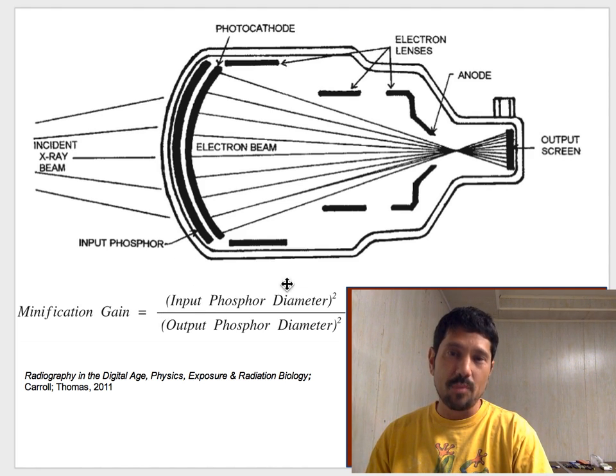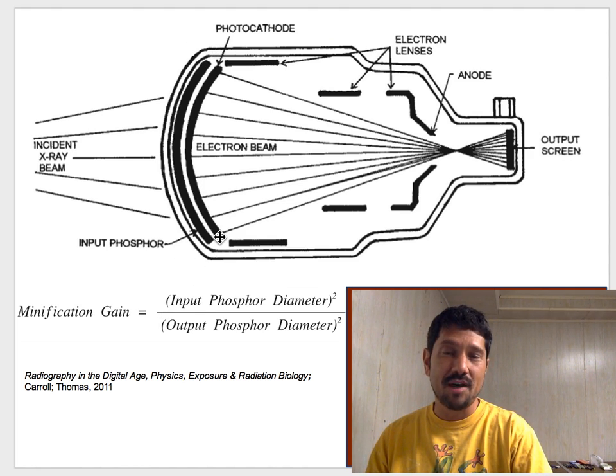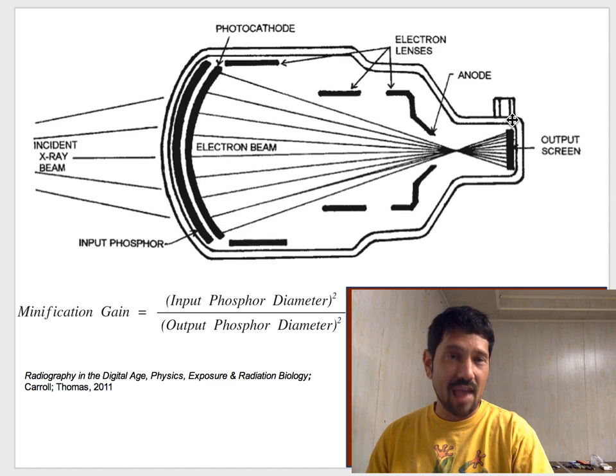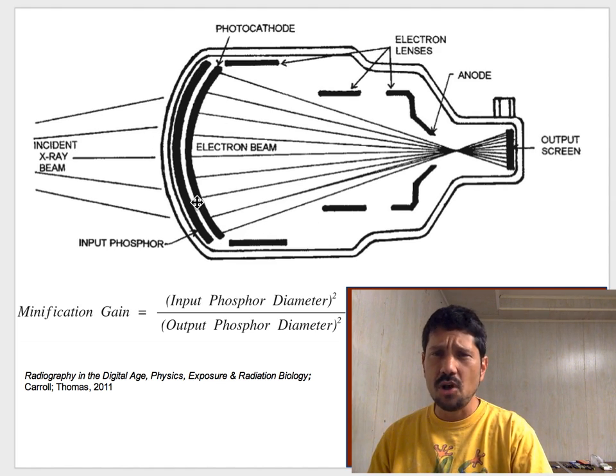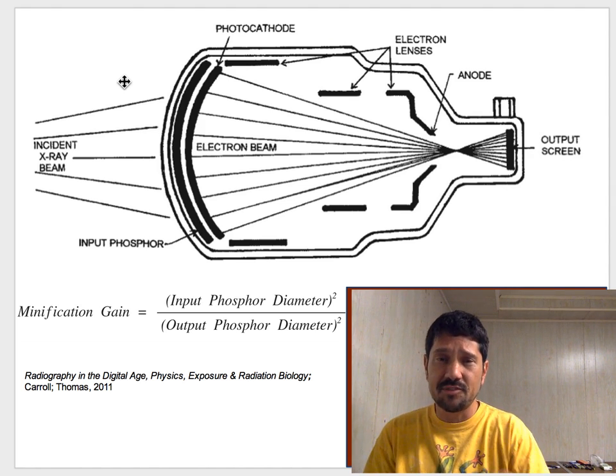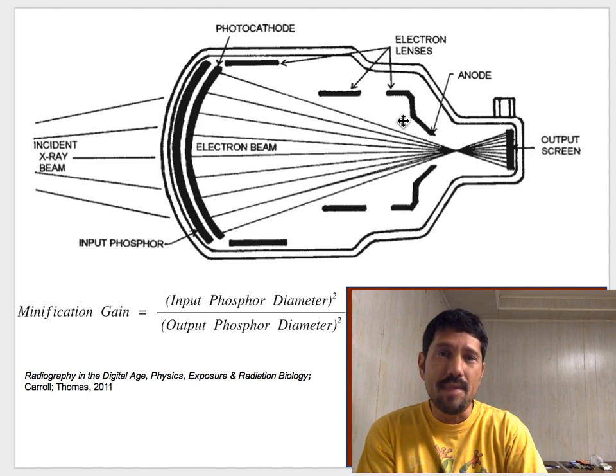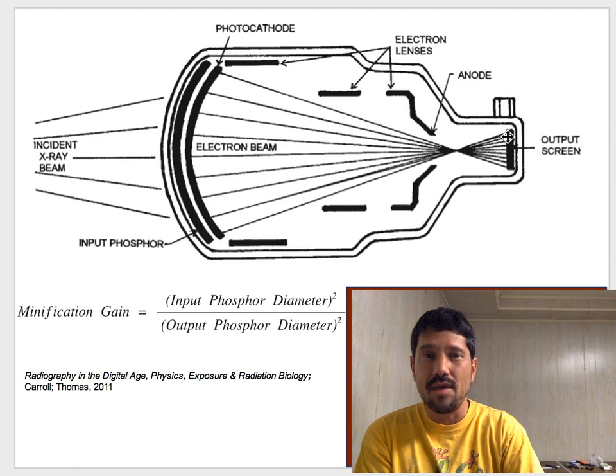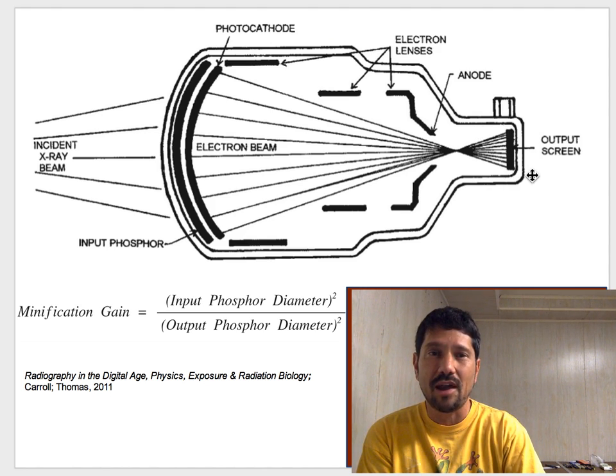And the minification gain will be based on the diameter of the input phosphor divided by the diameter of the output phosphor. So a lot of image intensifiers have 9-inch or 12-inch input phosphors, and then they minify the image because they've got to focus it onto a smaller area.